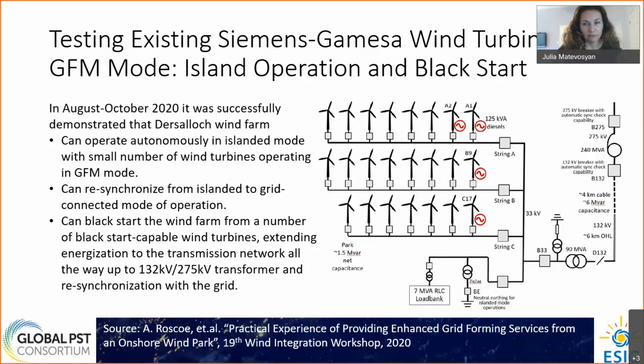You can see that the diesel is relatively small. It's 125 kVA, and just to put it into perspective, each turbine is 3.4 MVA. So the diesel powers up the auxiliaries of the wind turbine, and after that, the wind turbine can operate in grid forming mode and black start the rest of the island, and then be resynchronized with the rest of the grid. With just these 4 grid forming wind turbines with black start capability, they were able to energize the entire park, the 33 to 132 kV transformer, the overhead line, and all the way to the 132 to 275 kV transformer.